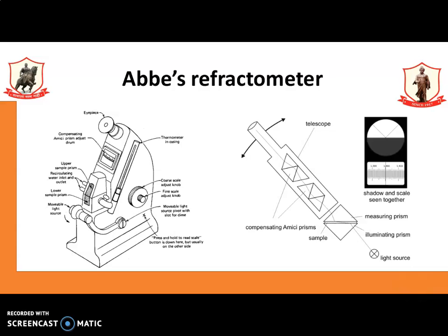These rays then pass through the polished surface of the upper prism and produce a critical boundary like a rainbow. This is due to the dispersion effect. To eliminate the color band, an auxiliary optical system called a compensator is incorporated in the telescope. You can see the telescope in the diagram, where the two Amici prisms are placed for the compensation.